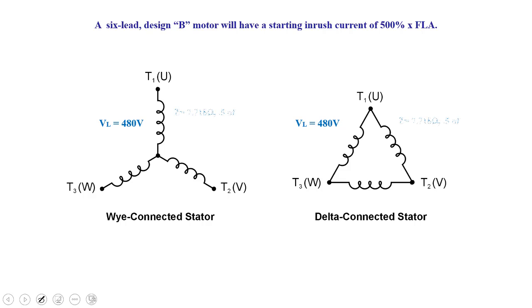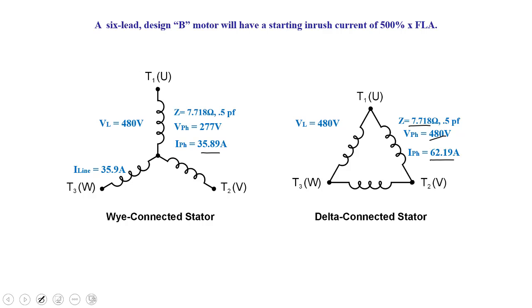So here we've got a 6-lead design B motor that will have a starting inrush current of about 500%. So if we were to go through this and figure this one out the same way, our phase voltage here, 480 divided by √3, is 277. Phase current is about 35.89, from 277 divided by 7.718 ohms. In delta, the phase voltage is 480, so 480 divided by 7.718 ohms is 62.19 amps. Line current is the same as phase current in Y. Line current is √3 higher in delta, 107.7 amps.